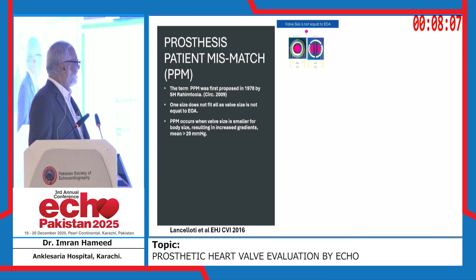Prosthesis patient mismatch occurs when valve size is smaller for body size, resulting in a mean gradient greater than 20. So what you do, you calculate projected effective orifice area, and here the chart comes to your help. You have the size and you have the effective orifice area. So this effective orifice area is to be divided by body surface area to get the reference that for this patient, at least a valve of this size should be implanted.